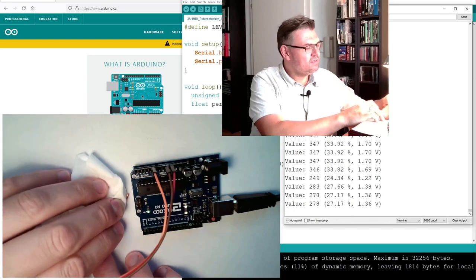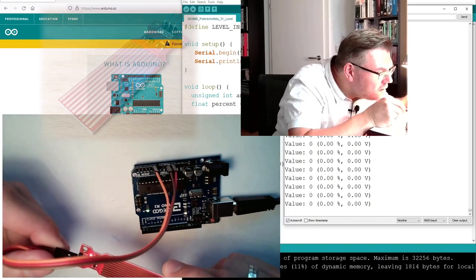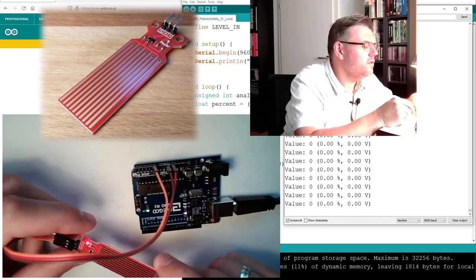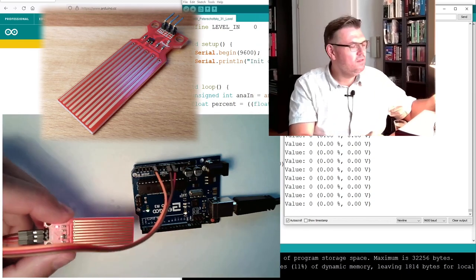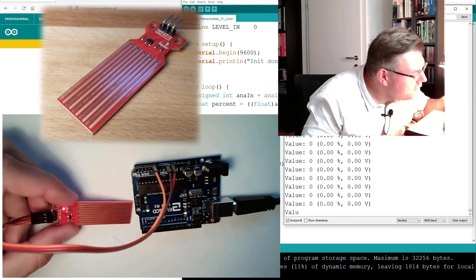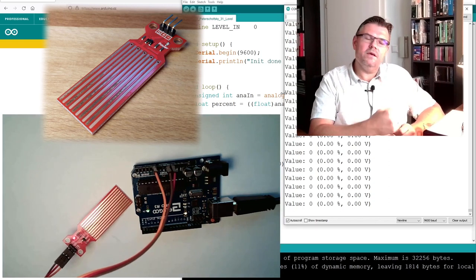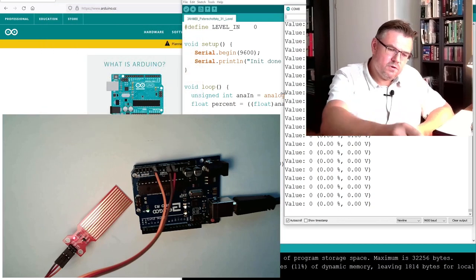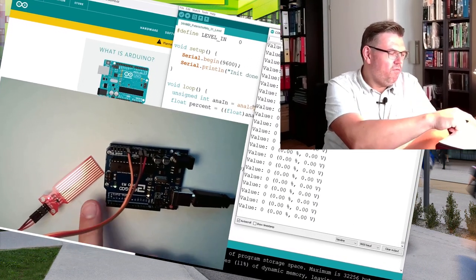The problem of this level sensor is that it really, see if we already see it here. Not yet, but every second has already a different color. There is wear, because if we want to transport current in the liquid, then we are using ions, and these ions will get off. It's like a galvanic dissolving.